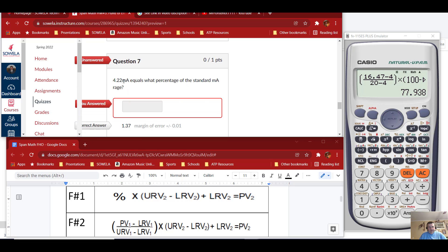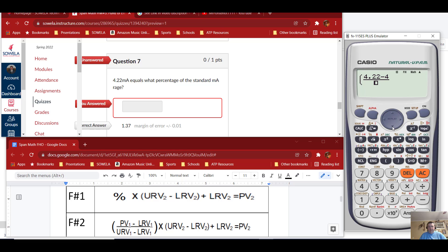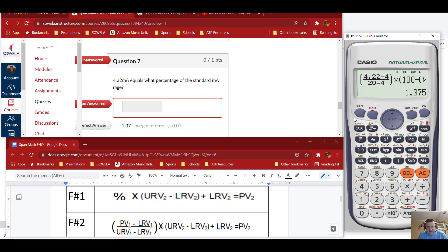Number 7: 4.22 milliamps equals what percentage? Again, looking for a percentage. Open parentheses, over-under: 4.22 minus 4, over 20 minus 4. I know it's going to be a very low percentage because I'm almost at the bottom of the span. Close parentheses, times, open parentheses — for percentage: 100 minus 0, plus 0. Equals 1.38%. I must have entered the answer slightly wrong in the assignment, but the margin of error of 0.01 allows it.